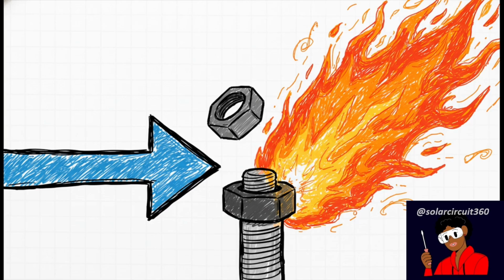Power equals current squared multiplied by resistance. Because the current is squared, doubling your current actually creates 4 times the amount of heat. Let's say you have a voltage loss of just 0.8 volts with 40 amps of current. That means your resistance is a mere 0.02 ohms. I mean, it sounds totally insignificant, right? But apply that to our heat formula, and suddenly, a surprisingly tiny resistance on a loose battery terminal becomes a massive thermal hazard when the system is under a heavy load.